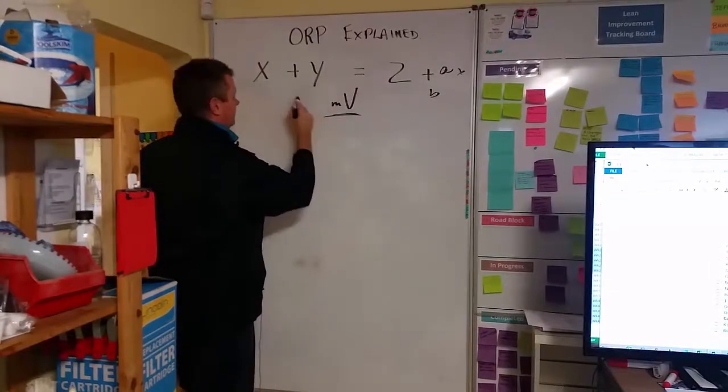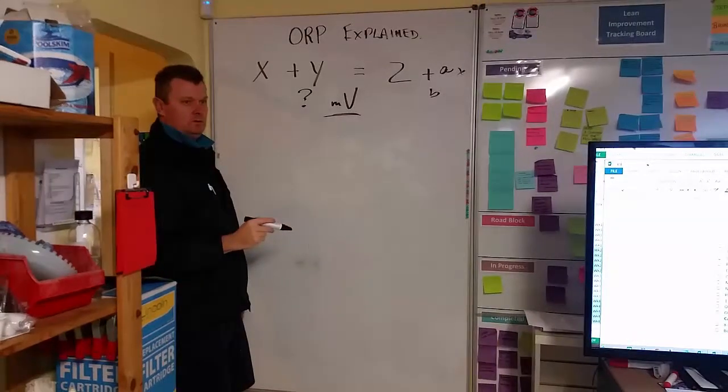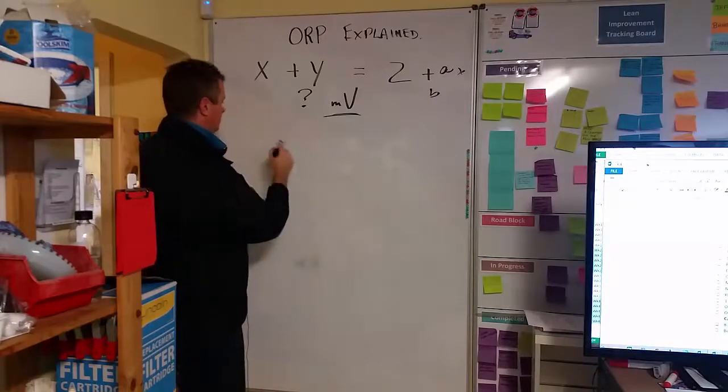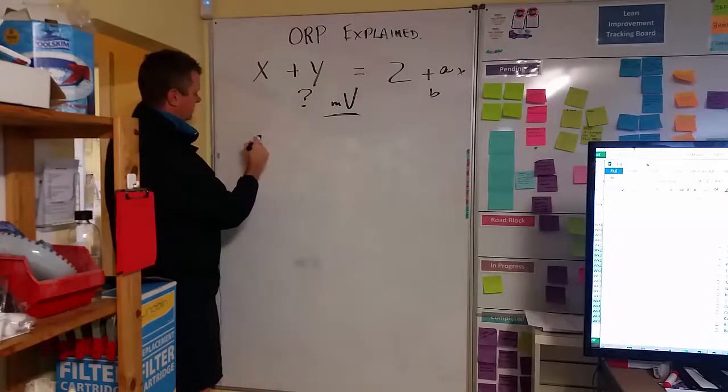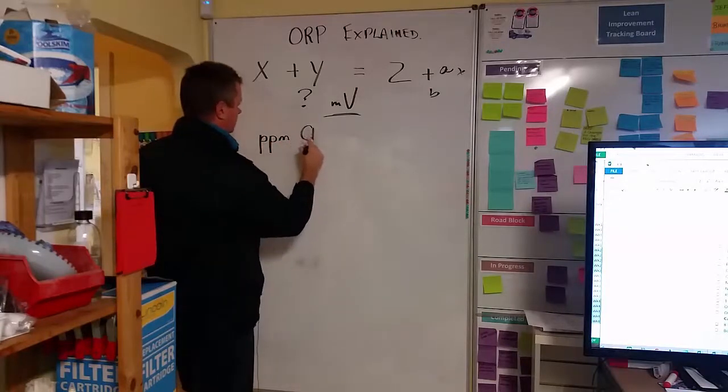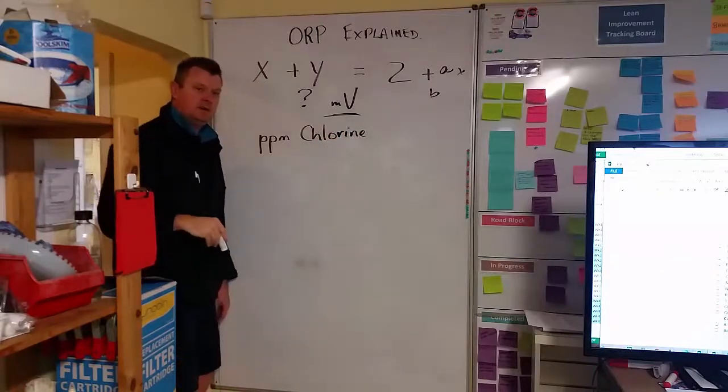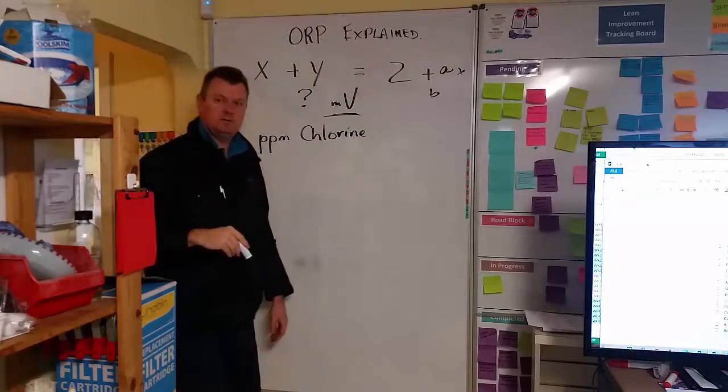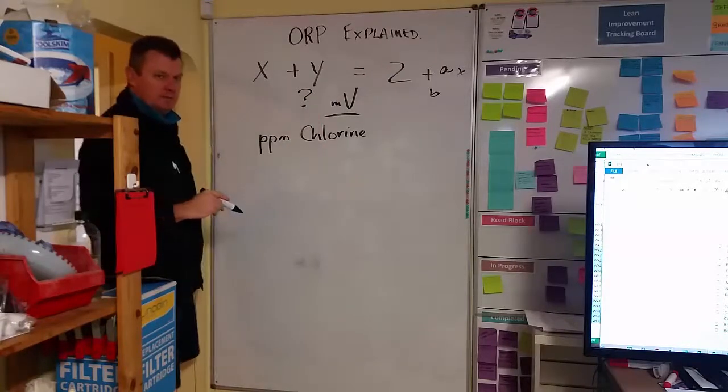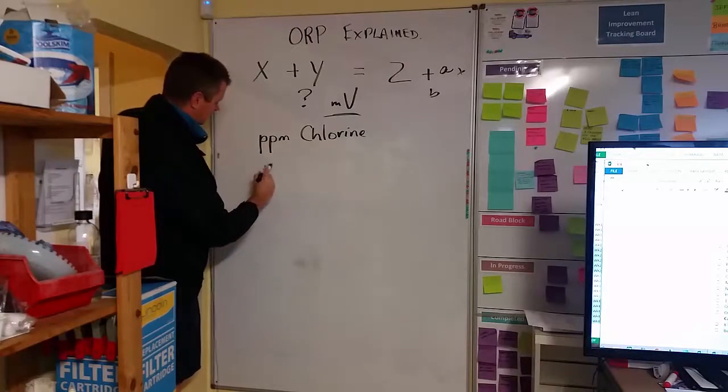That millivolt reading is affected by a few different parameters, so it's a very flexible thing. So, of course, it follows that PPM chlorine is a big factor. If you have no chlorine in the water, you don't have a lot of killing power in the water. So, as we've said before about pH, pH is another big factor.